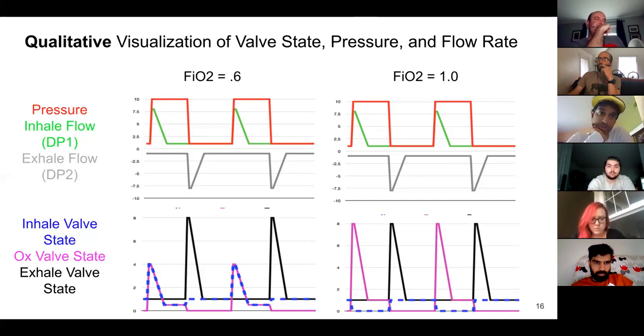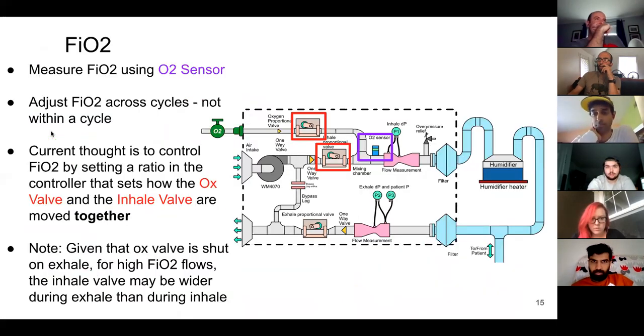I have a question regarding the control design. Not really the control design, just the hardware part of it. I know this is very strongly a pressure control based system right now, and at least some physicians are concerned about having volume-based inputs. I wonder if this architecture would be able to accommodate that without any changes, or rather, if it's a matter of software control.